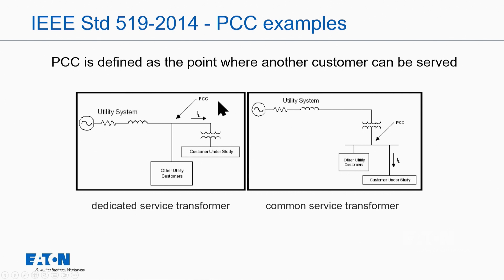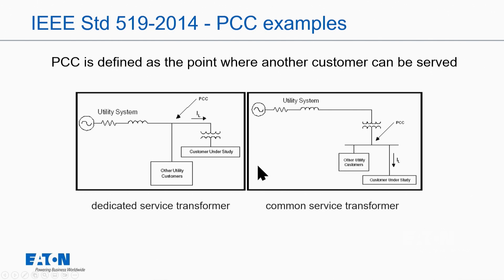This was pulled out of the 2014 standard, but it's also the same in the 2022 one. The point of common coupling is where we have a dedicated service transformer or a common service transformer. It could be either side — it just really depends on where the utility could feed another customer. The standard requires two things: you can't exceed a certain amount of total demand distortion from a current standpoint, and you can't exceed voltage harmonic distortion limits.